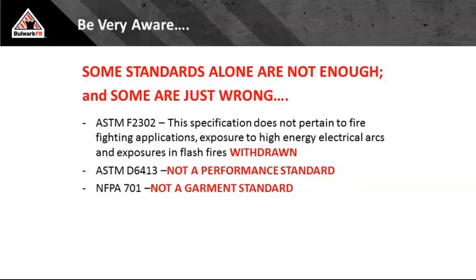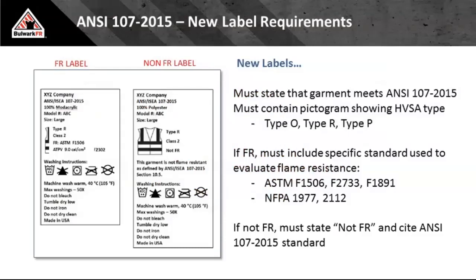It will fail miserably in an arc flash. We have tested it. We have seen it. We know it. NFPA 701, we see this in reflective vests. Be very cautious. This is not even a garment standard. You have no idea how that vest will perform in your hazard because it's not been tested to it.